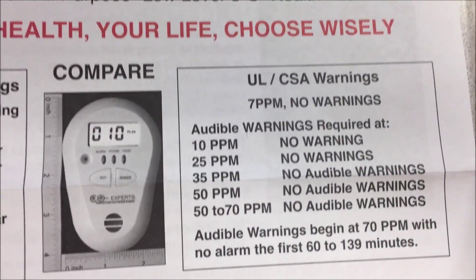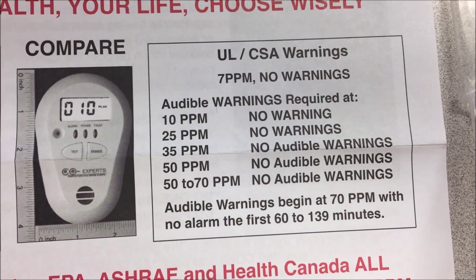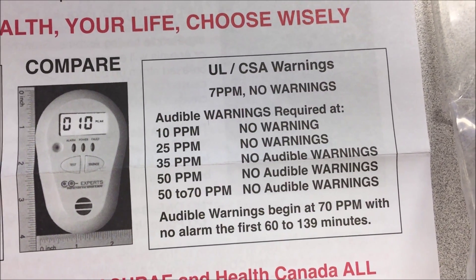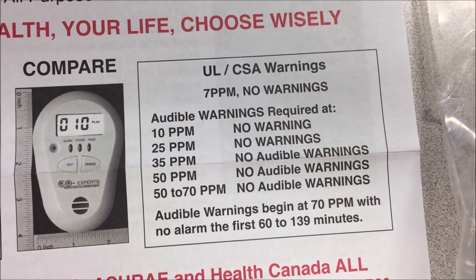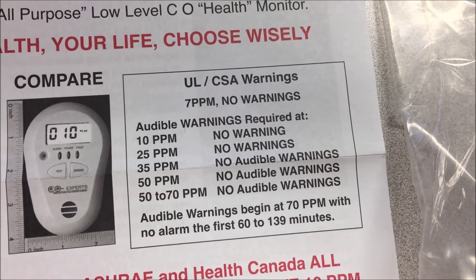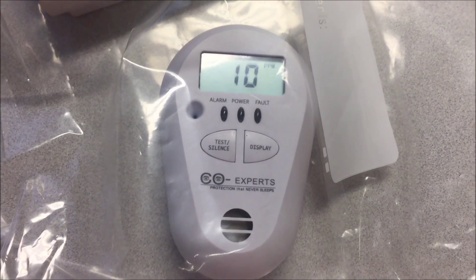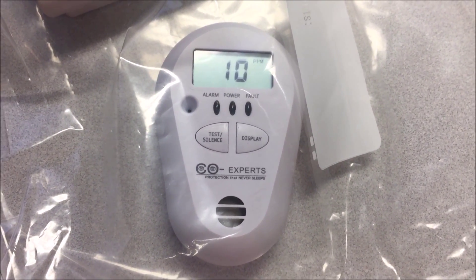A UL or CSA listed monitor will give zero warnings at seven parts per million, or ten, or 25, or 35, or 50. It has to be up to 70 parts per million, and there's not going to be an alarm for an hour — so it has to be a long-term exposure to 70 parts per million or more. Whereas with the CO-Experts, even at ten parts per million we're getting an audible alarm and a visual display of what's going on.